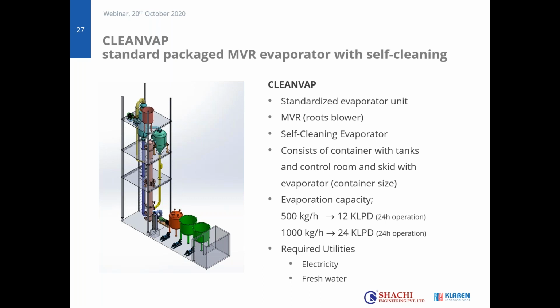So there is also a question about why not go for cleaning mechanisms. Well, in fact, if you need to clean the unit, you need to take it offline. And first of all, you start with fouling, so you do have lost capacity. If you need to clean it, it will take you time, it will take you chemicals, it will take you energy, because the system has to be up to temperature. So at the end, if there's really a fouling issue and people experience it, when we get the questions every day, then there will be a business case to go to self-cleaning.